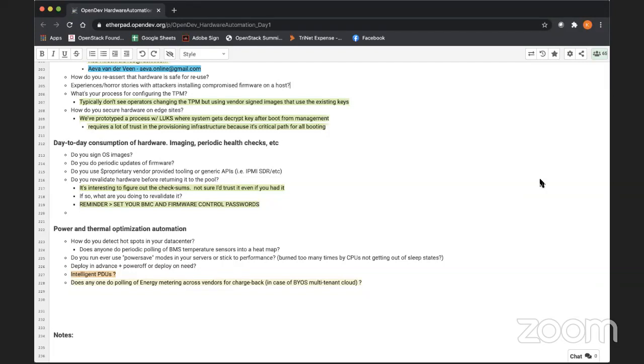We also set up alerting that's based on the limits that are published by the exporters. Different machines obviously have different temperature limits for their inlet and outlet temperatures. For example, the GPU heavy machines that have the GPUs in the front, their inlets need to be a lot lower than the normal machines that will take room temperature going in. And so that's an interesting thing that we do on that.